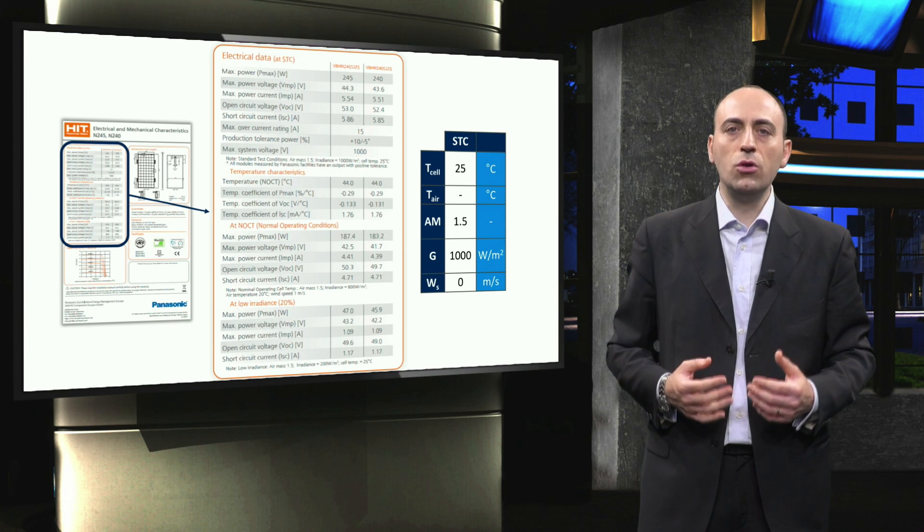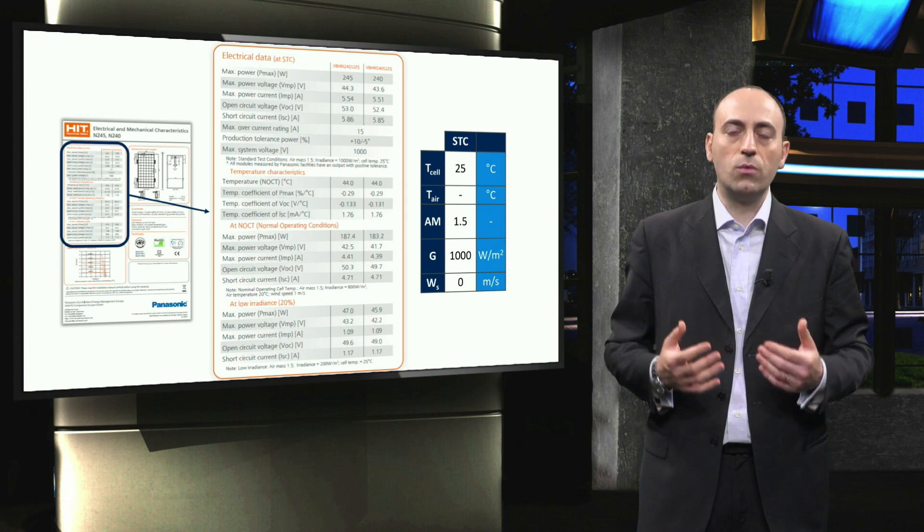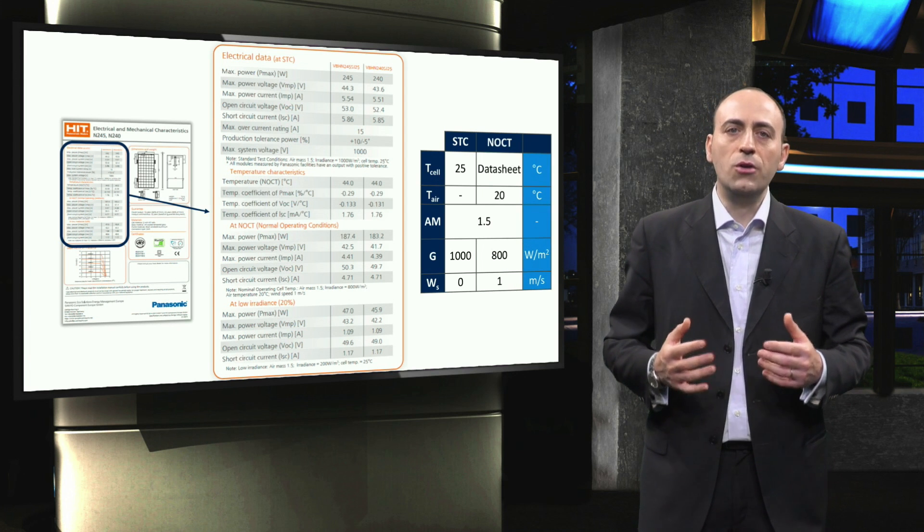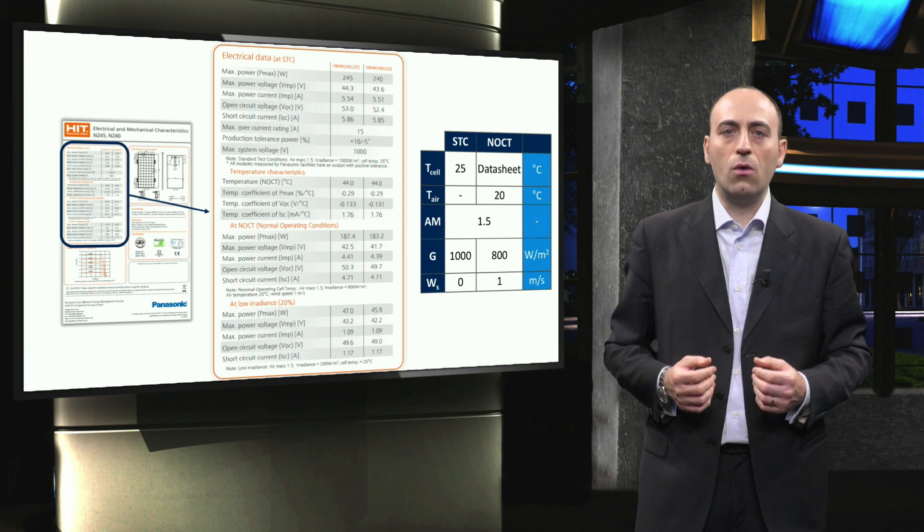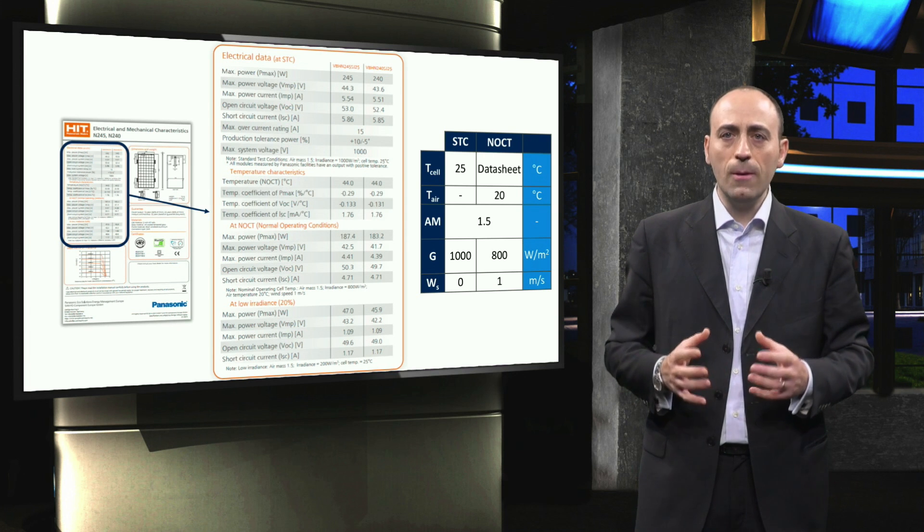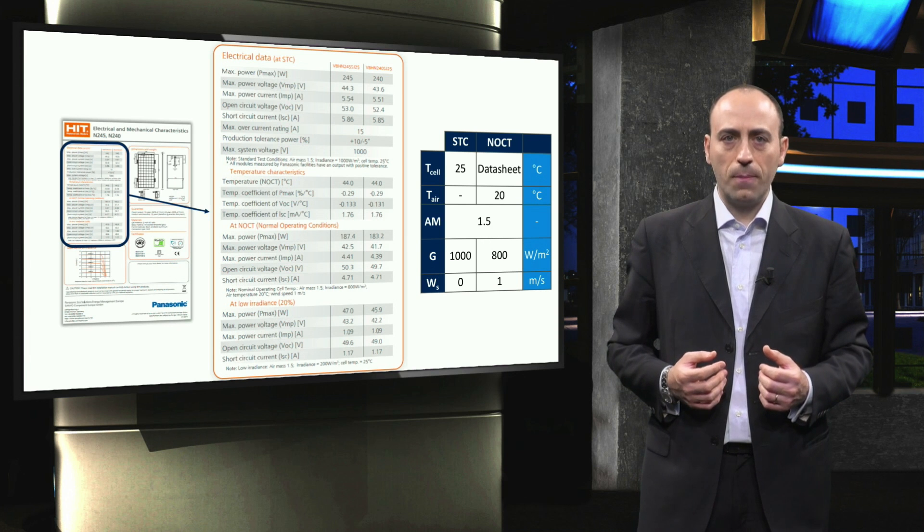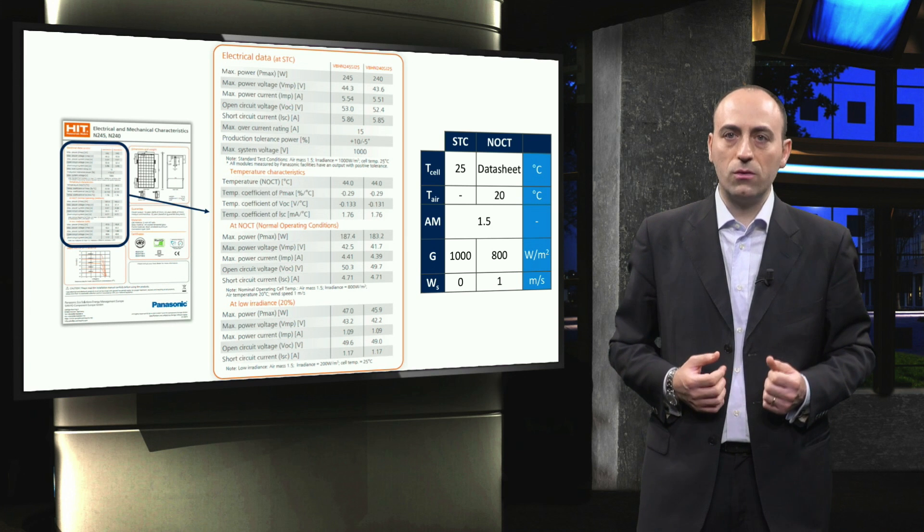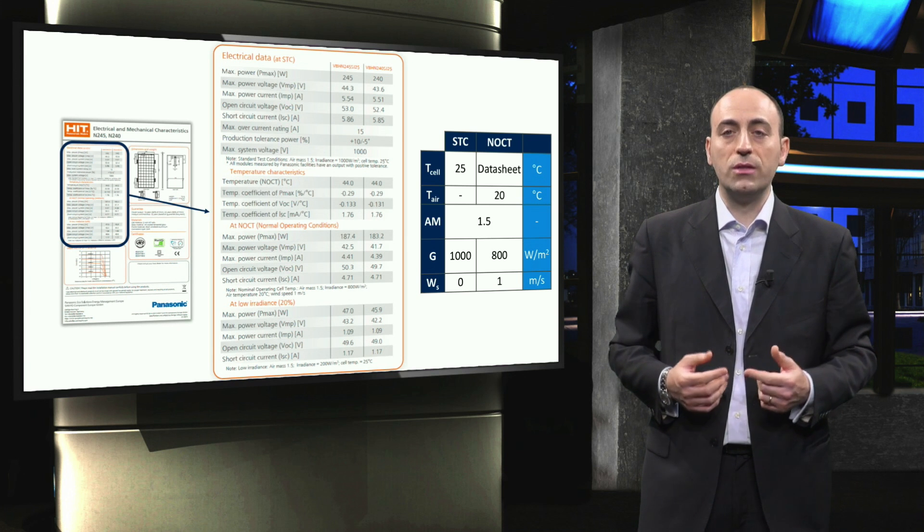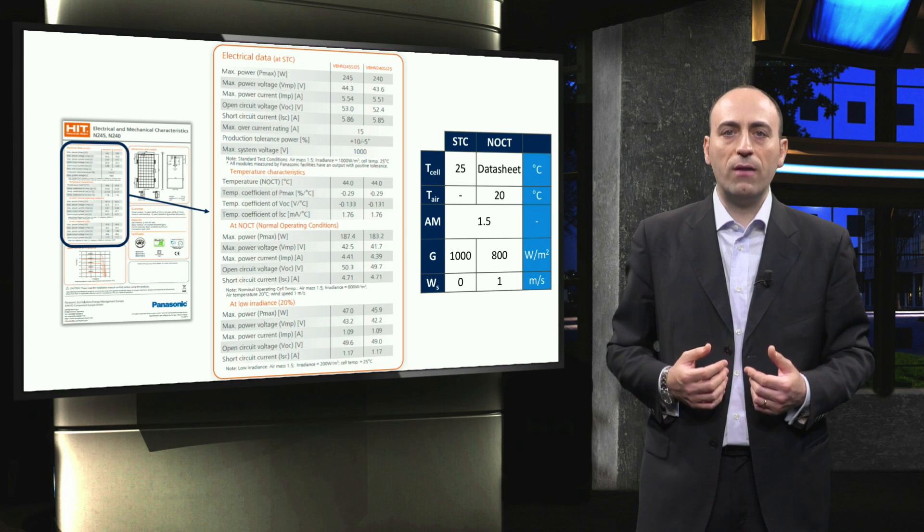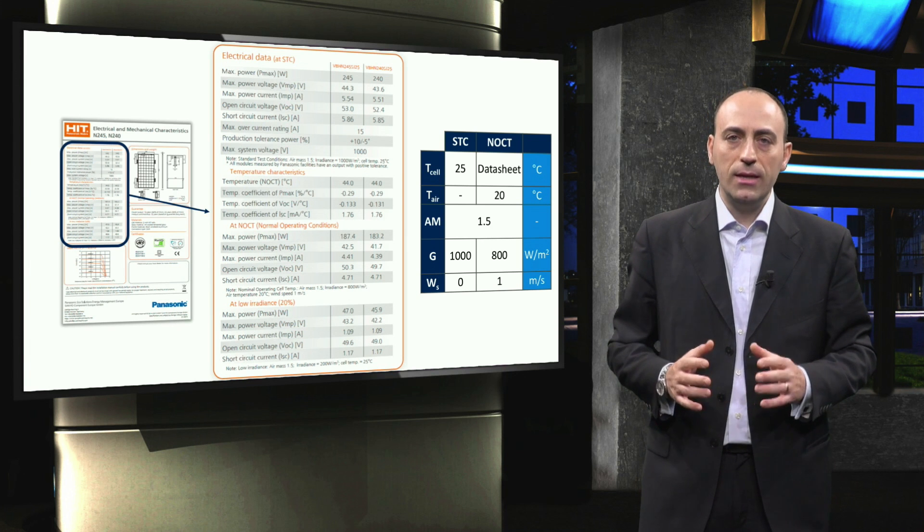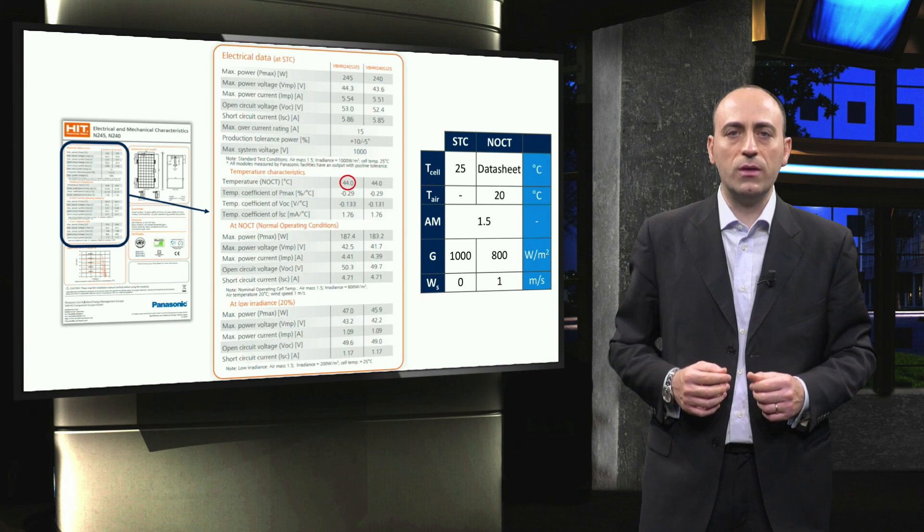However, under outdoor conditions, the modules are typically at a higher temperature than 25 degrees Celsius and at lower irradiance conditions. Therefore, the nominal operating cell temperature of a PV module is provided in the datasheet. This NOCT is the temperature at which the module will operate when it is under open-circuit conditions, when the air temperature is 20 degrees Celsius, the AM 1.5 solar irradiance is equal to 800 Watt per square meter, and the wind velocity is 1 meter per second. In this example, the NOCT is 44 degrees Celsius.